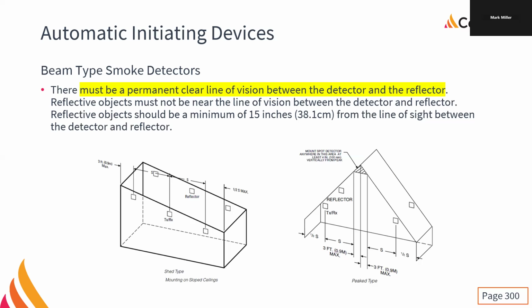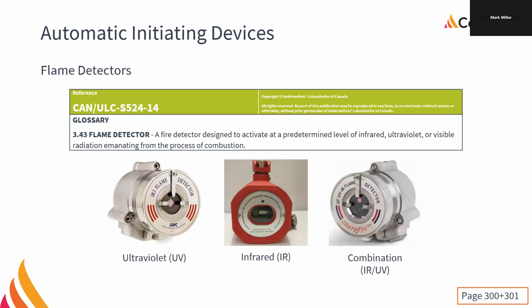The most fun I've had installing detectors is with flame detectors. I've done two jobs with flame detectors. The one I was a baby apprentice, a long time ago. We put in flame detectors in a canola oil testing laboratory because it was a laboratory, a federal building. It was a laboratory looking at different ways of extracting canola oil, right? Efficiencies and different ways of doing it and all that stuff. And of course, canola oil is flammable, especially when you're extracting it under pressure, all sorts of issues.